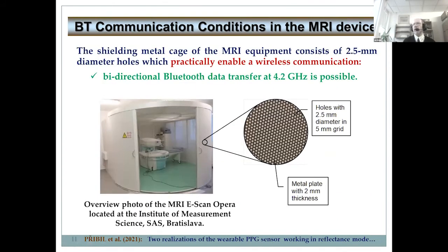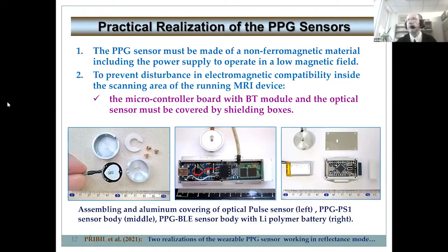As documented on this slide, the shielding cage around the MRI device consists of metal plates with 2.5 millimeter diameter holes. So the wireless Bluetooth communication running at 2.4 gigahertz is principally possible. To prevent disturbance in electromagnetic compatibility inside the scanning area of the running MRI device, all parts of the PPG sensor must be covered by non-ferromagnetic materials, as documented by the 3 photos introduced below.